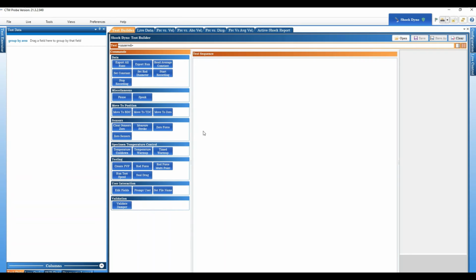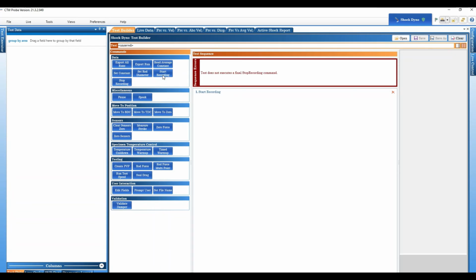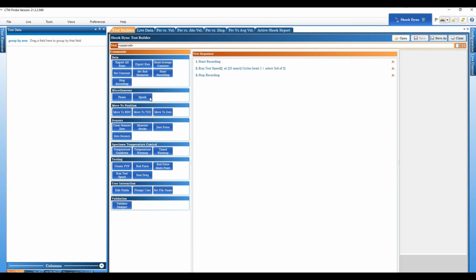And we have a video for building tests, but the first place you're going to go to is Test Builder, and you're going to build a test from there. Now, a test is very simple or very complex, just based on exactly what you need. If you wanted one speed and nothing else, it would be as simple as doing a start recording, run test speed, stop recording, and then move to bottom. That's a test. All done.